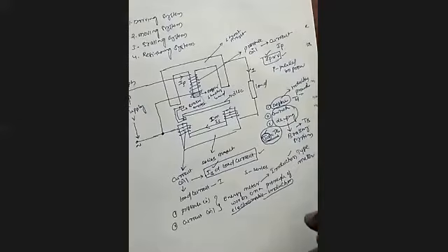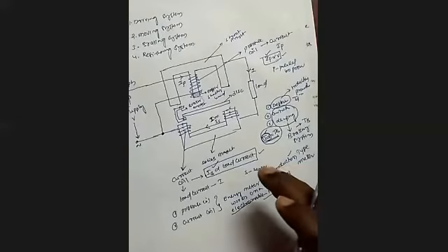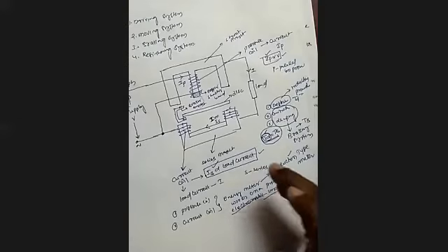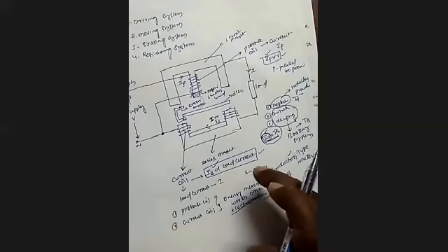So here we clearly understand that for the production of torque in an induction type energy meter or induction type instrument, whatever the measuring instrument working on the principle of induction, the machine should require two fields, or two fluxes. Because of those two fluxes, there is a development of EMFs. Due to those induced EMFs, there is a development of torque.